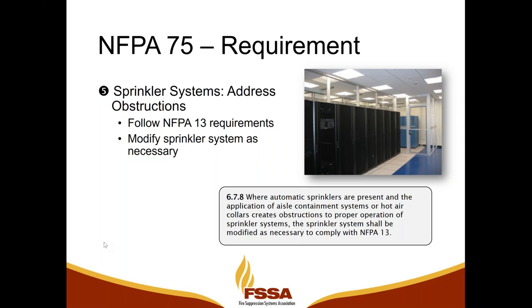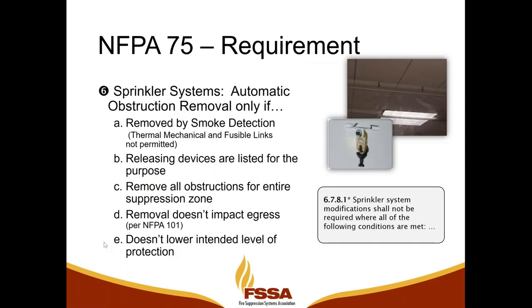That's now called for. Also, for automatic obstruction removal, meaning automatic removal of the aisle containment system, it's allowed, okay, but only if it's removed via smoke detection. So we need to have an electronic device that helps remove the system once the smoke detectors in the space see that there's smoke before the sprinklers operate. And then the releasing devices to remove the obstruction must be listed for that purpose.